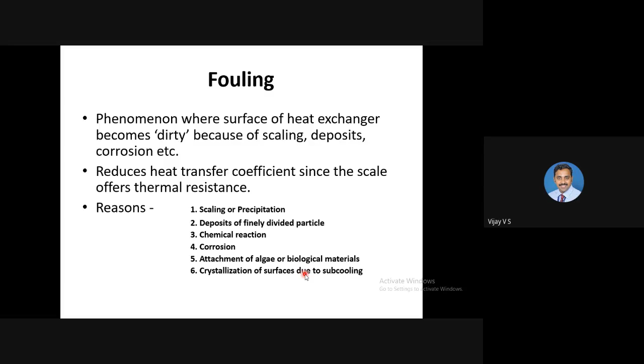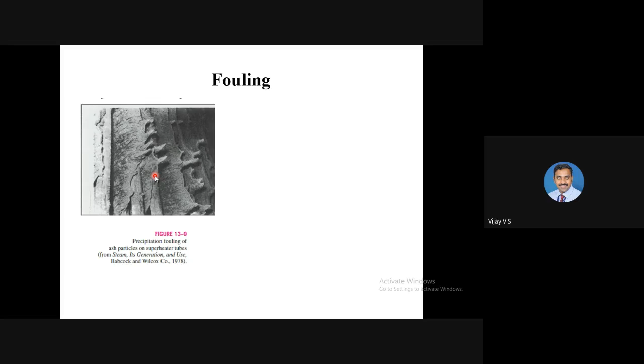See, this figure shows how the pipe looks after a long run. This figure is taken from a Babcock and Wilcox boiler. It shows precipitation fouling of ash particles on superheater tubes. This is the outside surface of the tube. Inside, water is flowing, outside are the hot gases, and you can see the ash deposited. If you allow the heat exchanger to run with this much precipitation, you can see how much heat has been lost. So the resistance I calculated previously, I cannot use the same resistance.